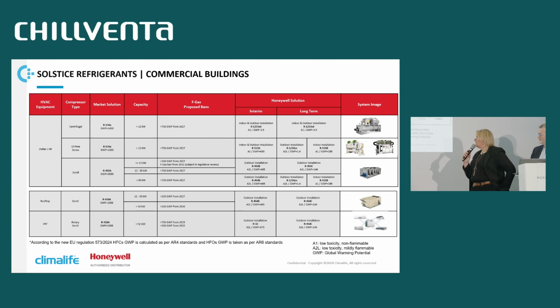It's a long-term solution for this application. Today it's clear we are using R32, but do not forget that with F-gas regulation we will have some bans, particularly from 2027, for 12 to 50 kilowatt units, and for more than 50 kilowatt rooftop units, in 2030 you need to use refrigerant with GWP less than 150.